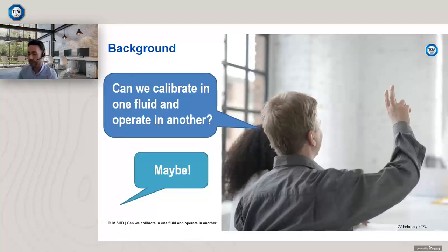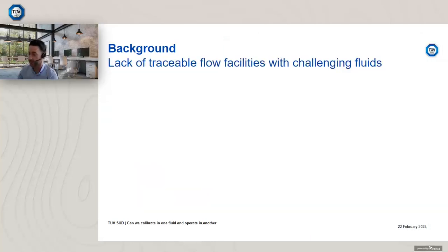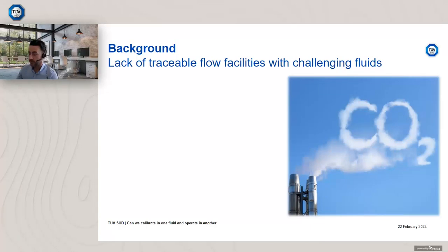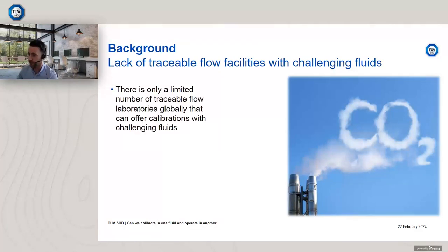They're referring to newer, challenging applications. So applications with other fluids such as CO2. One of the main challenges, the reason why we're asked it, is that there's a lack of flow facilities, or traceable flow facilities, shall I say, that offer these new challenging fluids. Obviously, they're not new fluids, but the applications are becoming more widespread, and there's definitely a requirement for things such as CO2 measurement. However, there's only a limited number of traceable flow laboratories globally that can offer calibrations with challenging fluids.